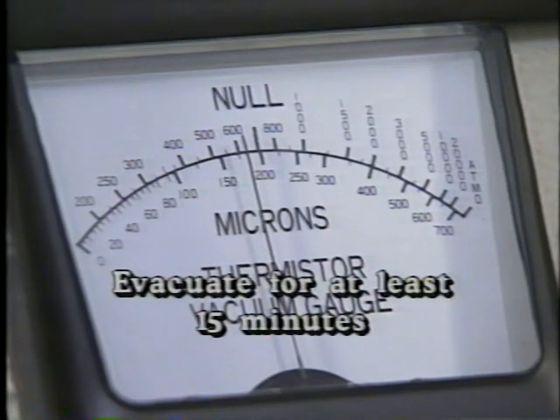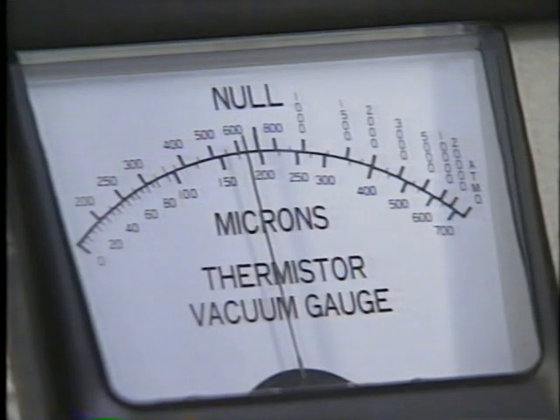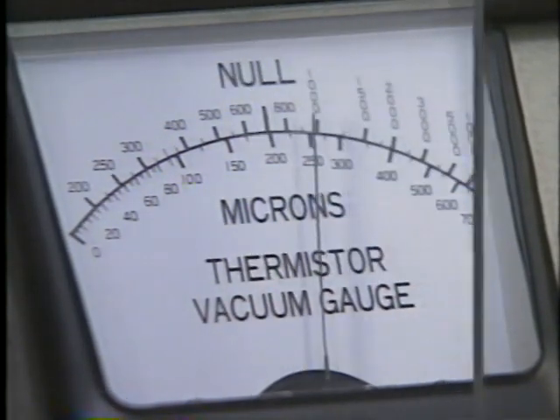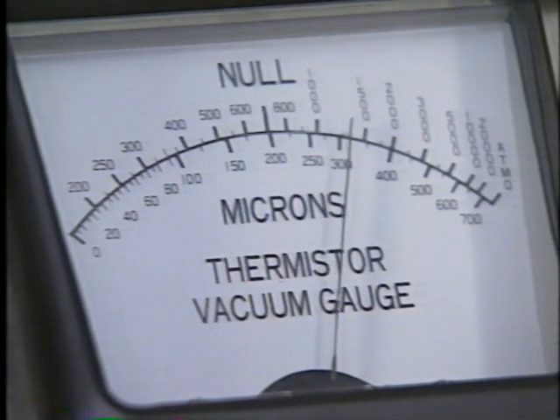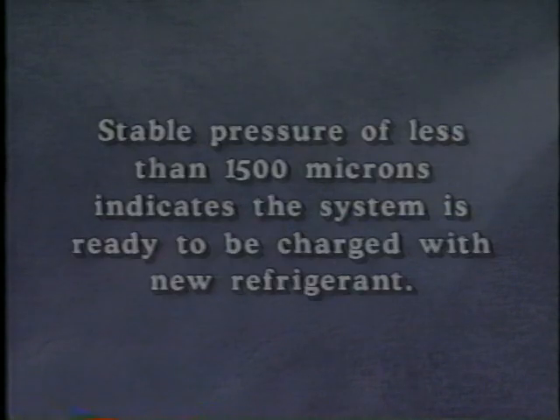Evacuate for at least 15 minutes, then shut the vacuum pump down and observe the thermistor. If there is any moisture in the system, the pressure will rise. Continue to evacuate the system. If there's a system leak, the pressure will soar. Repair the leak. Once the thermistor indicates a stable pressure of less than 1,500 microns, the system is ready to be charged with new refrigerant.